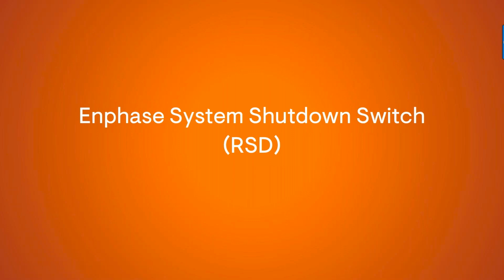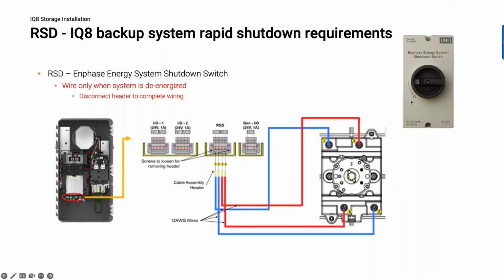A couple of remaining last critical topics. There are a number of errors being made, and I want to make sure we cover this in terms of best practices. The first is related to the Enphase system shutdown switch, or the rapid shutdown device. You're probably familiar with this. If you're installing any kind of Enphase backup system using IQ8, you have to put this device in. Some installers have asked, why do I have to put in this RSD, rapid shutdown switch, when I usually have just a rapid shutdown blade switch? Or can't I use the circuit breaker within the combiner box to do rapid shutdown?